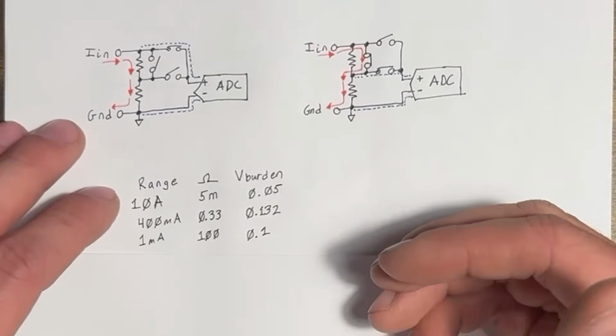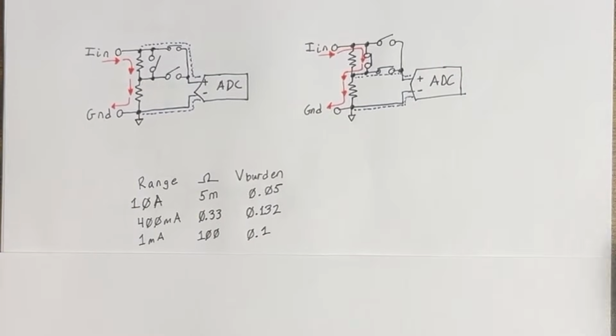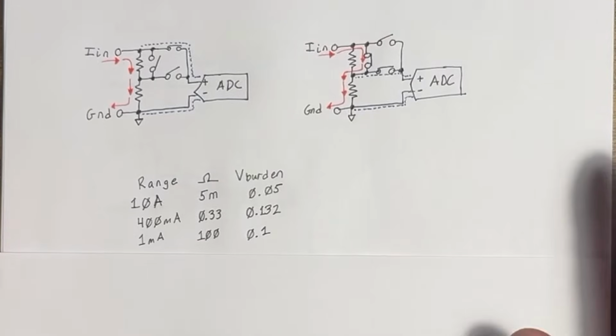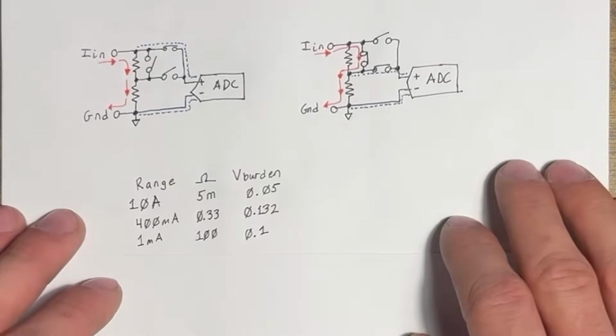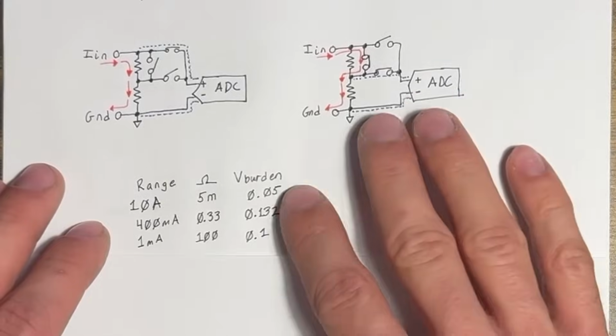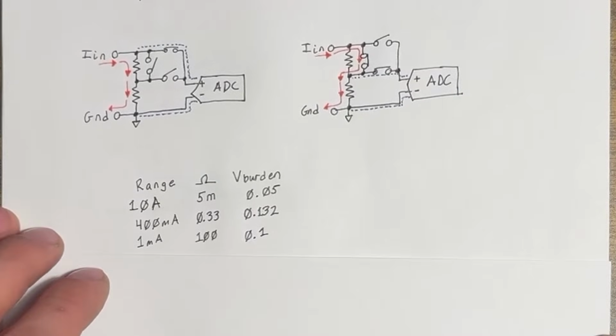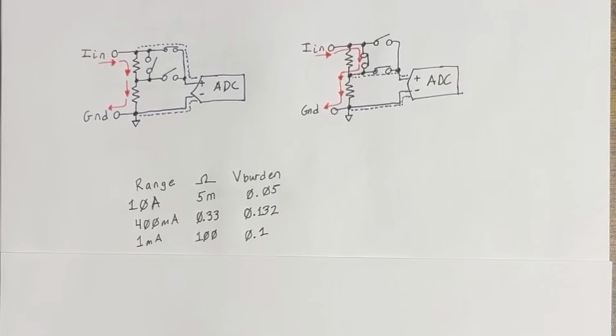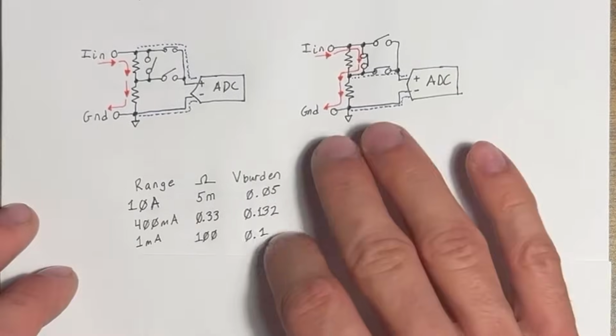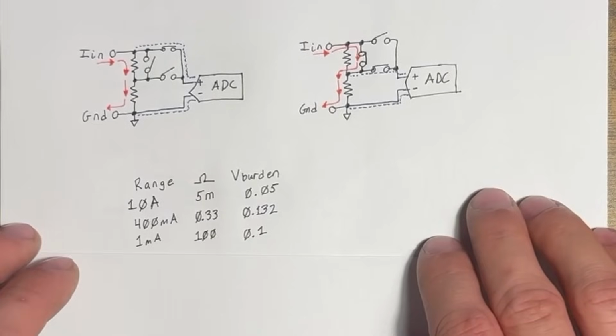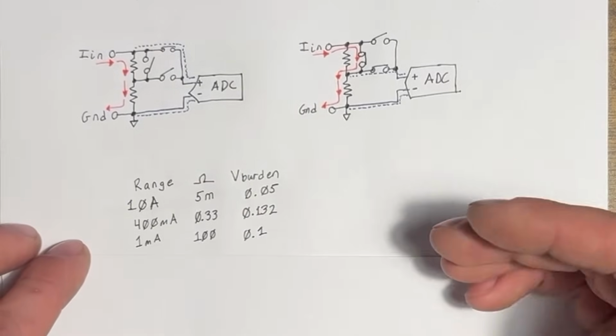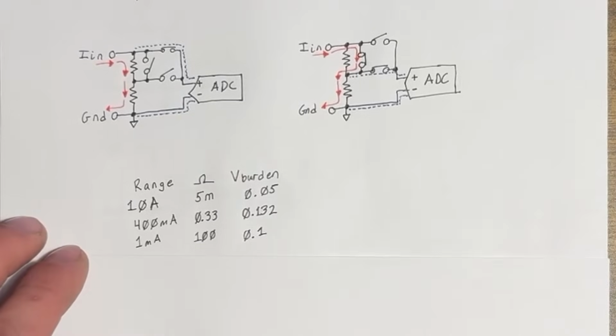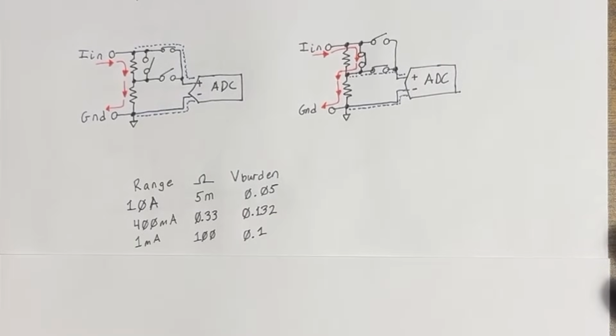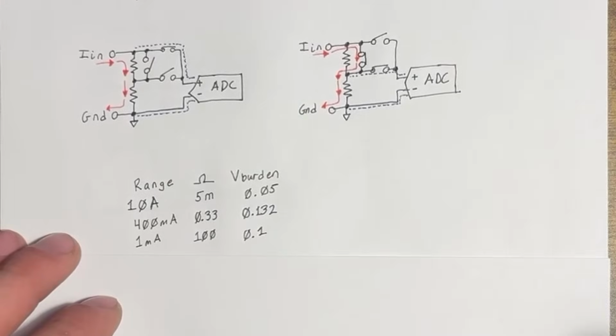One of the big things we want to minimize in our current range is the voltage that drops from input to output. As we push current through the meter, we have to measure a voltage across there. In theory we could use Hall effect or something like that, but we're not doing that here. So we want to keep that voltage down, preferably around 100 millivolts or so - we could go lower or higher, but I wanted it around there. For the 10 amp range we also have to worry about power dissipated in that resistor - 100 millivolts at 10 amps would be a full watt, so we want to keep that down.